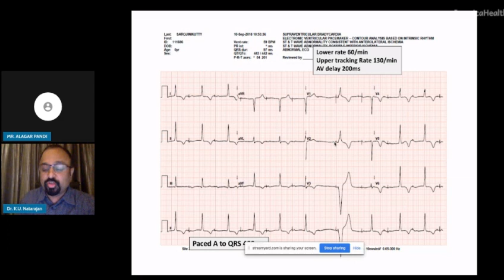And this long gap has resulted in a backup ventricular pacing. So this is again not an abnormal pacing function. It is a normal pacing function. The pacemaker shifts from AAI pacing to ventricular based pacing here because of the long gap without a QRS complex. So you should know that modern day pacemakers function perfectly well before you venture into identifying whether the pacemaker is functioning normally or abnormally on the basis of your ECG.